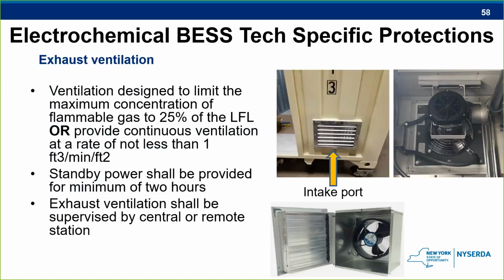So maybe not lithium ion, but some systems do need ventilation for a battery during the charging. Some may be releasing hydrogen as part of that. So in that case, the developer would need to install a ventilation fan, perhaps for a walk-in, with battery chemistries other than lithium ion. It could be used for lithium ion systems as a method of explosion control, and we'll talk about that in a couple of slides too.